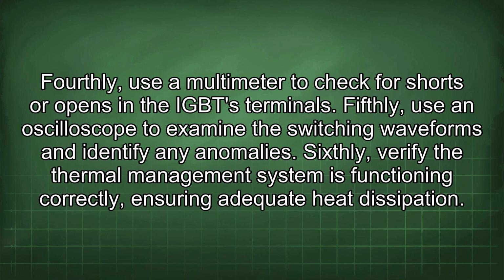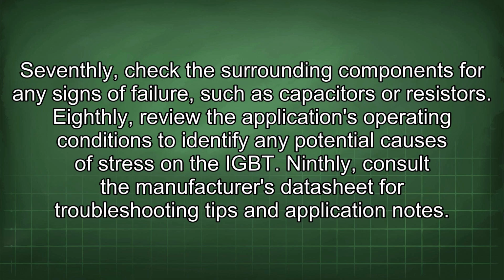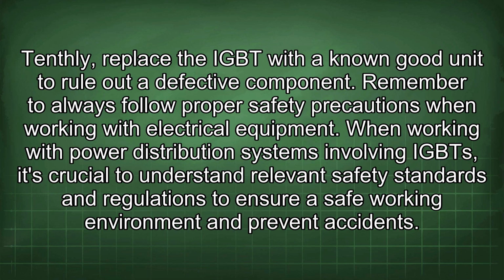Sixthly, verify the thermal management system is functioning correctly, ensuring adequate heat dissipation. Seventhly, check the surrounding components for any signs of failure, such as capacitors or resistors. Eighthly, review the application's operating conditions to identify any potential causes of stress on the IGBT. Ninthly, consult the manufacturer's datasheet for troubleshooting tips and application notes. Tenthly, replace the IGBT with a known good unit to rule out a defective component. Remember to always follow proper safety precautions when working with electrical equipment.